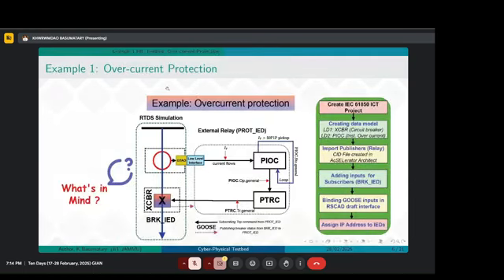First, when we are thinking about testbed development, somebody has to think in his or her mind about what I want to achieve from the testbed. For example, suppose I would like to implement overcurrent protection. I can't test it directly in the physical grid, so that's why I'm simulating it in the RTDS. Suppose this one is the distribution line feeder you have, and you have the protection relay here, and you would like to trip this breaker inside the RTDS right now.